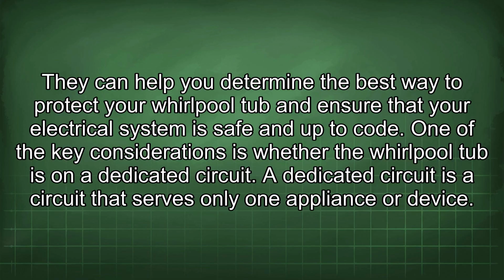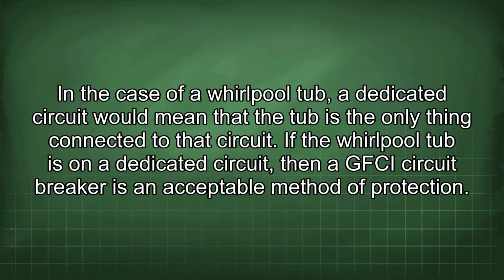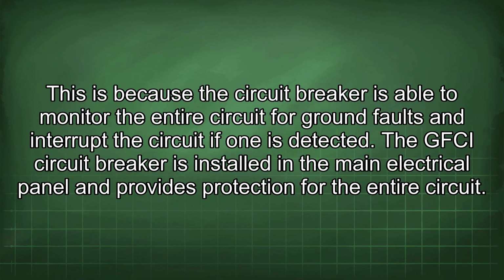One of the key considerations is whether the Whirlpool tub is on a dedicated circuit. A dedicated circuit is a circuit that serves only one appliance or device. In the case of a Whirlpool tub, a dedicated circuit would mean that the tub is the only thing connected to that circuit. If the Whirlpool tub is on a dedicated circuit, then a GFCI circuit breaker is an acceptable method of protection. This is because the circuit breaker is able to monitor the entire circuit for ground faults and interrupt the circuit if one is detected.